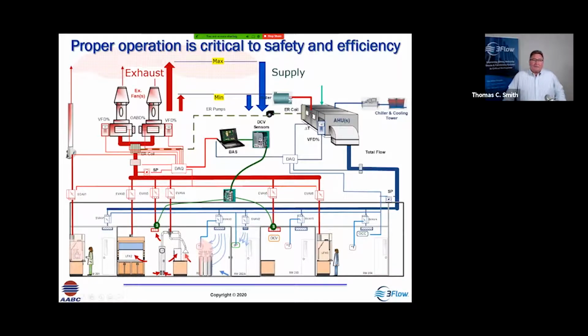So one of the big questions becomes, if we're going to save energy, if we move the flow through the hood, we modulate flow, how does that translate to a reduction in flow through the systems? What's that VAV sensitivity that modulates flow? Well, we also know that the energy consumption is mainly associated with HVAC operation. So how much flow is going through the building and how much it's being conditioned. And so that conditioning and transport of the flow are the major energy components. And so when we look at the major factors driving energy consumption, it's going to be HVAC, number one, 45 to 85% of the energy is associated with HVAC. We have plug load, maybe that's 25 to 30%. And we have lights, which may be 5 to 10%. And then there are some other miscellaneous factors that associate with energy consumption.